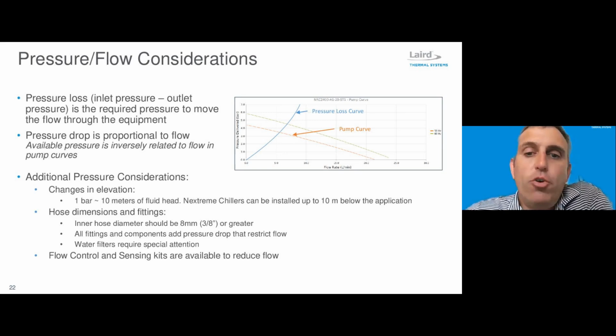In applications that require less flow than what the pump can deliver, there are a number of ways that you can get to that operating point. We offer an optional kit that consists of a bypass valve assembly as well as a flow meter, so you're able to really dial in exactly what that flow rate is. And this is usually sufficient for most applications, because they tend to have a single operating point that is set up at the time of install.